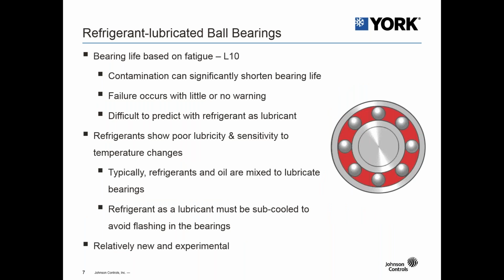Also, it's similar to what you would see on an oil lubricated system. These bearings would still have an L10 bearing life. So that would be, on average, the life of the bearing, how long it would last through run hours. And you still have concerns about contamination, so that's why there's still a filter there, and contamination can significantly shorten the life of the bearing. Typically what we see on the refrigerant lubricated bearings is very little to no warning when a failure occurs, so it's very difficult to predict when you may need to do a bearing inspection or tear down or replacement. Failure occurs pretty quickly, so there's very little opportunity to do advanced maintenance or a scheduled shutdown and tear down.